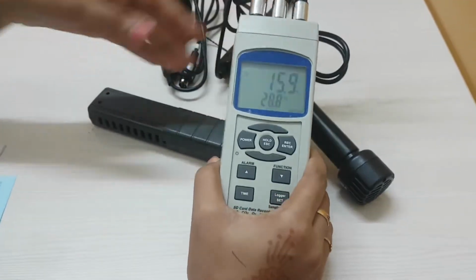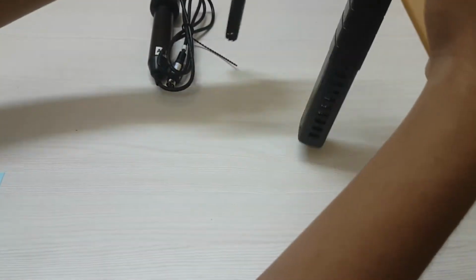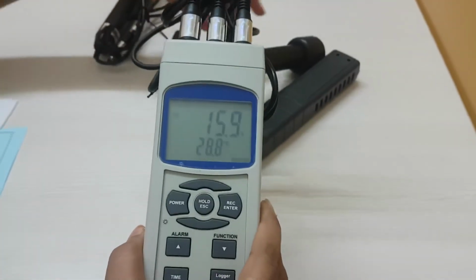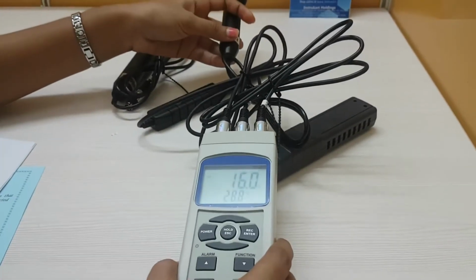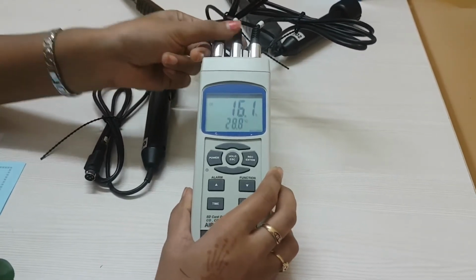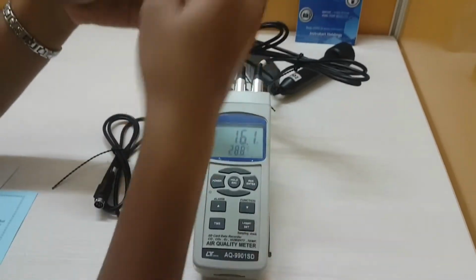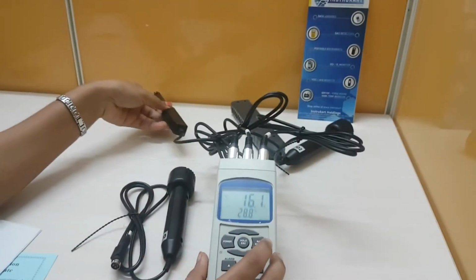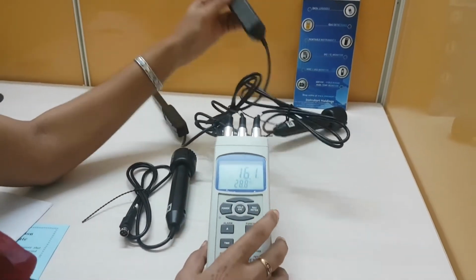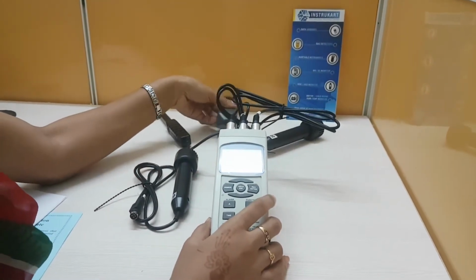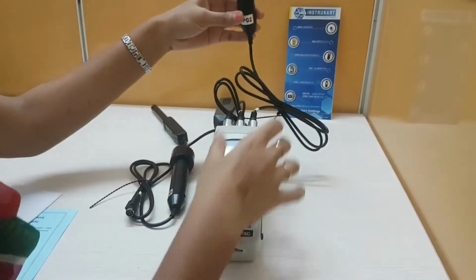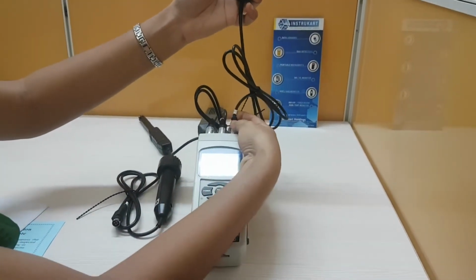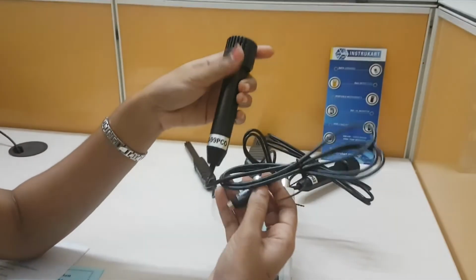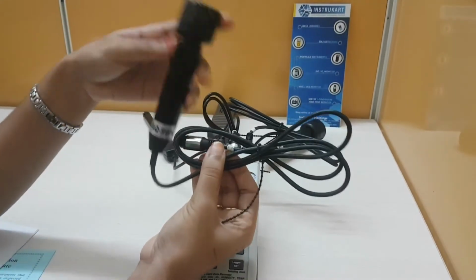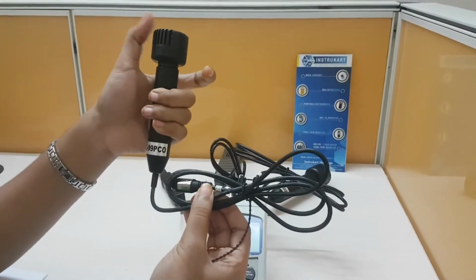I have connected all the probes. We have connected the probes. This is a humidity probe, humidity sensing area, and the probe input jack, and this is the CO2 probe, and here this is the oxygen one. Here you can see, and this is a CO probe, and this is a CO sensing head.